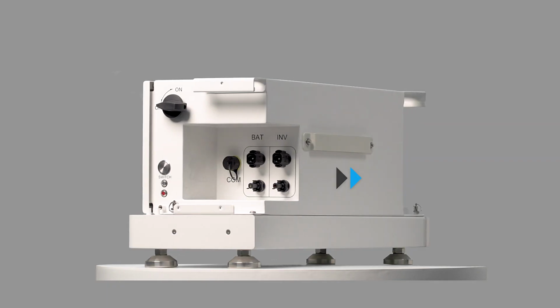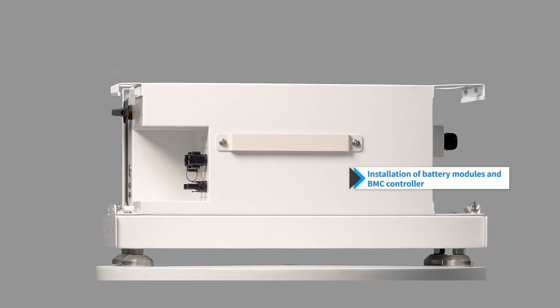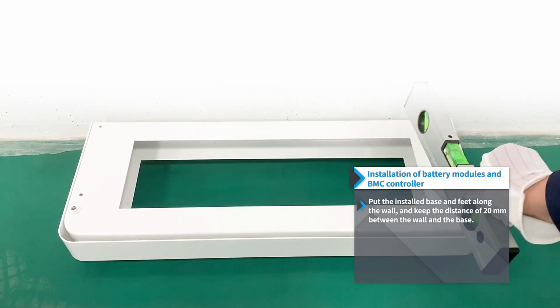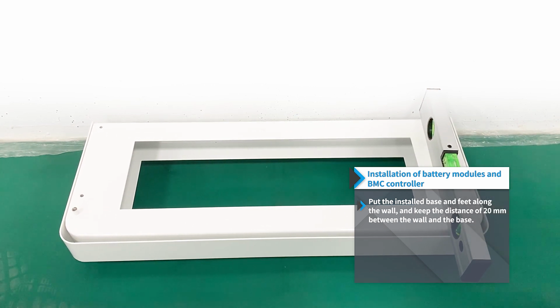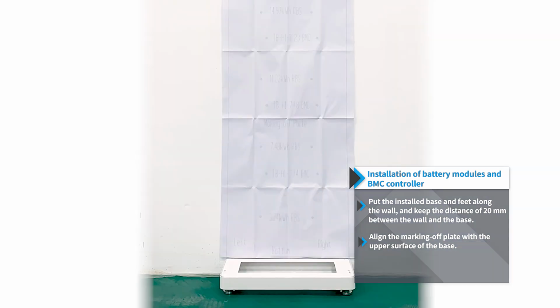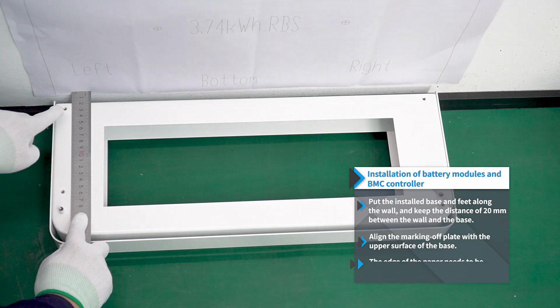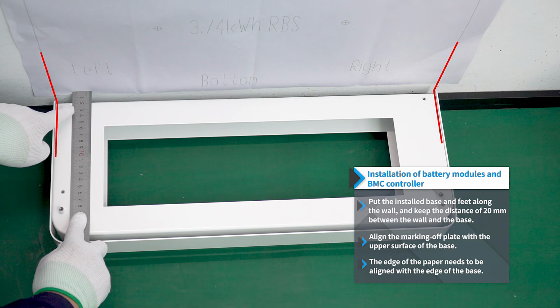Installation. Installation of battery modules and BMC controller. Put the installed base and feet along the wall, and keep a distance of 20 mm between the wall and the base. Align the marking-off plate with the upper surface of the base. The edge of the paper needs to be aligned with the edge of the base.